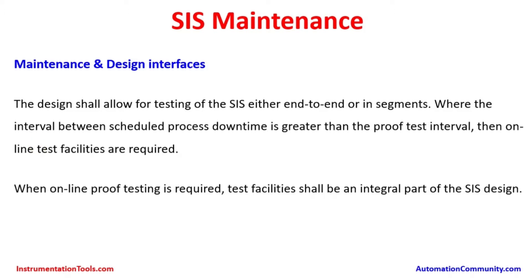The safety instrumented system shall be capable of doing maintenance on instrument devices. The design should be done in such a way that each instrument can be taken up for maintenance as required. When online proof testing is required, the test facility shall be an integral part of the design. In some cases there could be only one instrument which may not be able to be isolated while the process is running, so there shall be a provision to do online testing, and the design should have considered making such a provision.